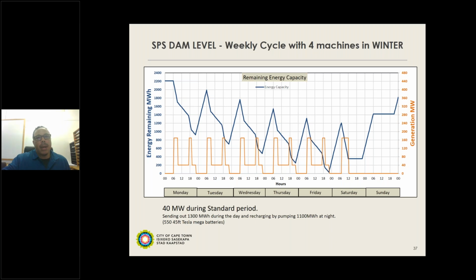So we don't pump back all the water that we generate, it takes too much energy and too long. For every hour that a unit is able to generate, it takes an hour and 20 minutes to pump that same volume of water back up. Hence you will see the declining peak on Tuesday, Wednesday, Thursday, all the way into the weekend. That's the blue line on this energy capacity graph, which is what it's trying to show.